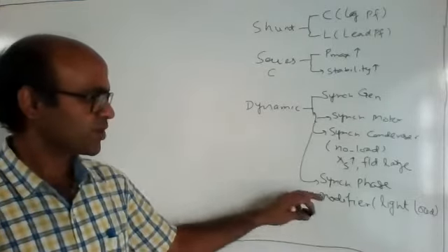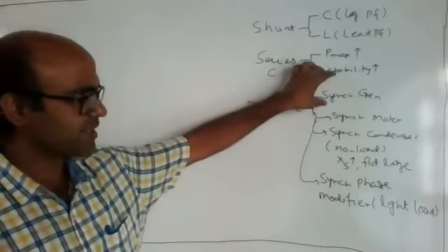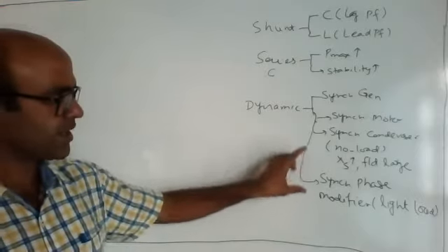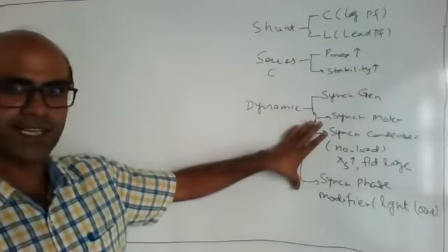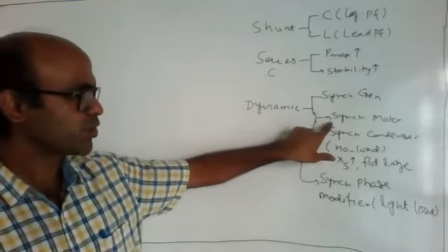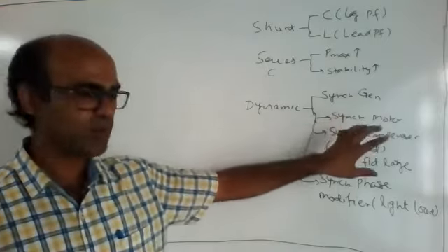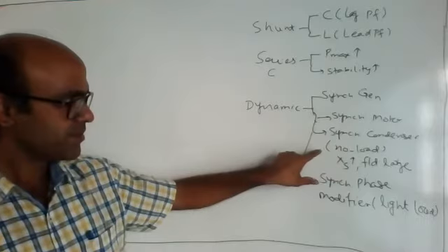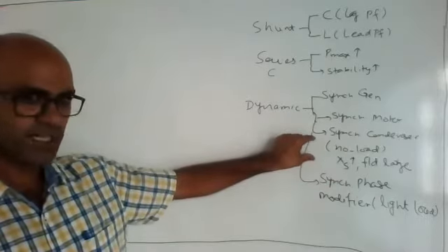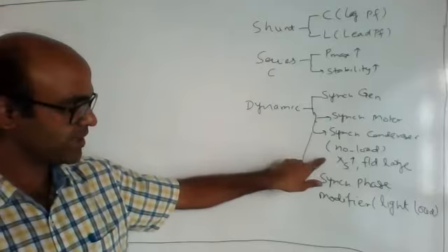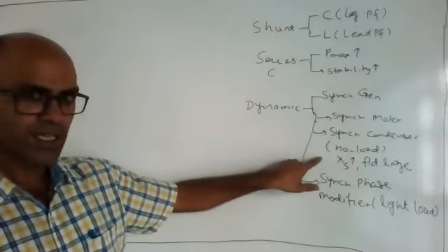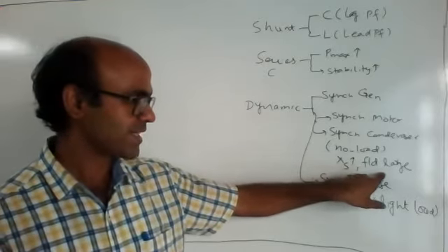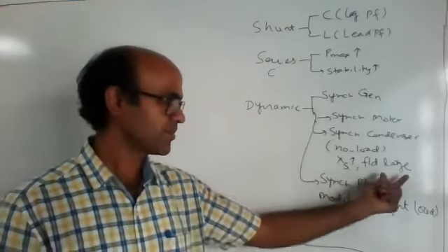So there is a slight difference between the synchronous generator and these three categories. These are all synchronous motors, but there is a difference in design and operating condition. If a normal synchronous motor is used, then we can improve power factor. If we are stabilizing voltage of large magnitude, then we will increase the synchronous reactance of the motor, as well as increase the rating of the field winding.